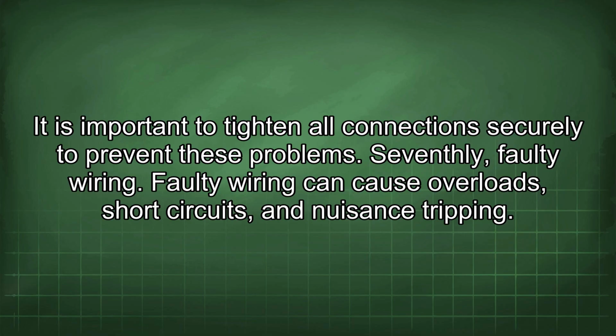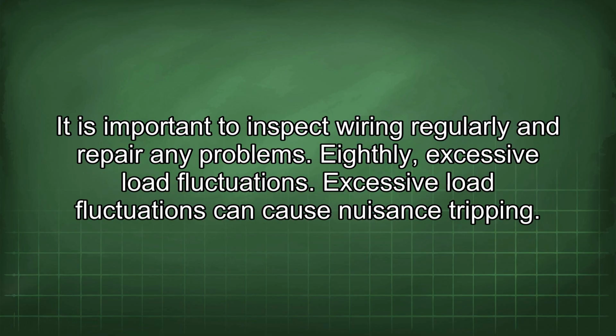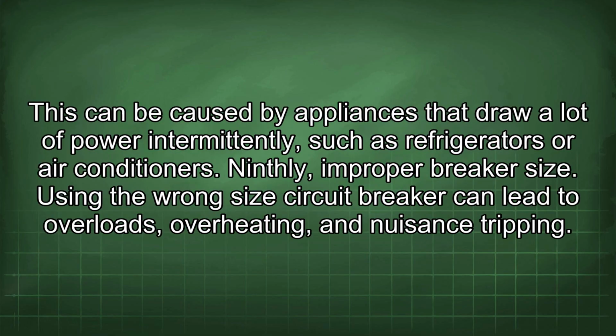Seventhly, faulty wiring. Faulty wiring can cause overloads, short circuits, and nuisance tripping. It is important to inspect wiring regularly and repair any problems. Eighthly, excessive load fluctuations. Excessive load fluctuations can cause nuisance tripping. This can be caused by appliances that draw a lot of power intermittently, such as refrigerators or air conditioners.